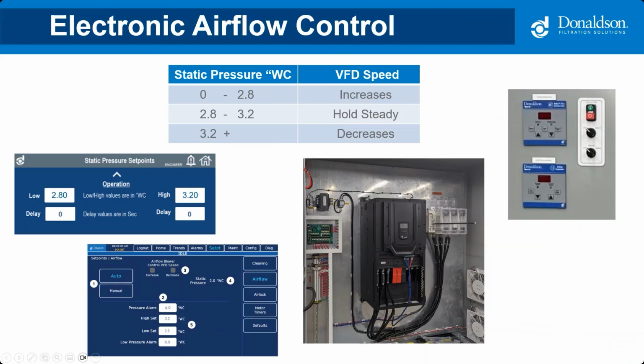I sure can. So Donaldson and Control Assemblies jointly developed a simple VFD airflow controller. The image on the right shows the Delta P Plus with an airflow controller as a separate component. The newer touchscreen options combine the cleaning controls and airflow control. Although the user interface may be different between these, the method is the same. Airflow control does require a variable frequency drive to control the speed of the main blower fan motor.